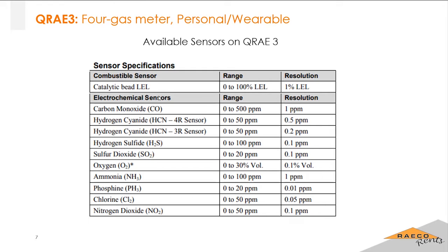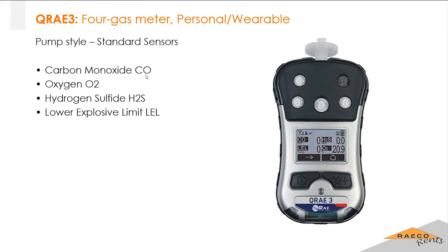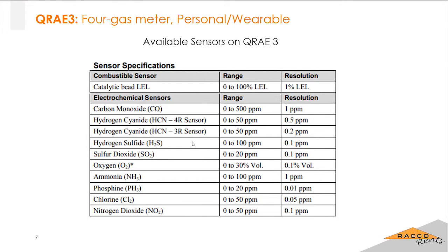And we have just the standard 4-gas sensors on it, which is your CO, oxygen, hydrogen sulfide, and the LEL sensor. I'm not sure if you guys know, but the LEL is the lower explosive limit. So that's going to give you a reading in percentage of that limit. You won't get parts per million like you would with carbon monoxide or hydrogen sulfide, but typically that's measuring methane, and it can be set to measure other combustible gases. So, another thing to think about, if there are combustible gases like methane or propane, pentane, just to name a few, you can adjust the sensor to respond to certain gases, kind of similar to a PID, which we'll go over later, but you guys might know about that already.